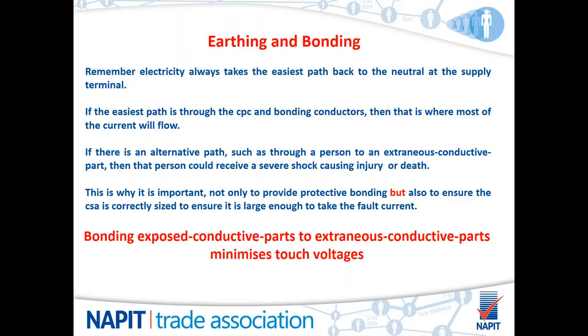Okay, so one thing to remember is electricity always takes the easiest path back to the neutral at the supply terminal. If the easiest path is through the CPC and bonding conductors, then that is where most of the current will flow. If an alternative path should arise, such as through a person to an extraneous conductive part, then that person could receive a severe shock causing injury or death. This is essentially why it is important not only to provide protective bonding, but also to ensure the cross-sectional area is correctly sized to ensure it is large enough to take the fault current.